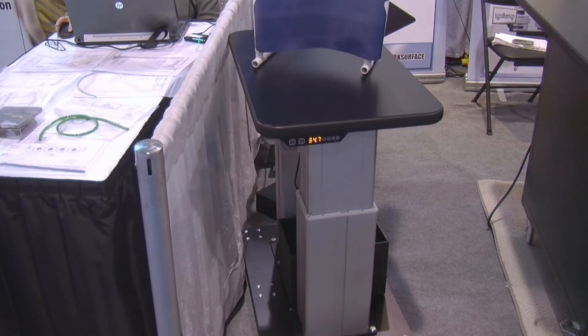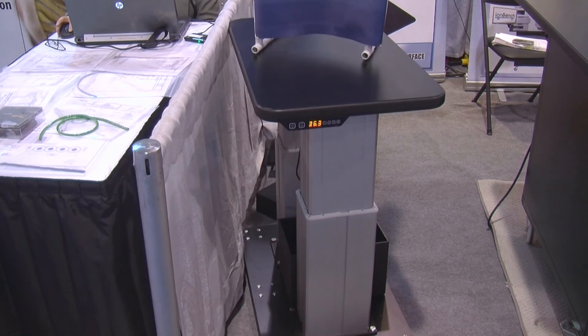The LC cart includes many features such as solvent waste and a power cord at the rear, so that all LC modules are connected directly into the cart. This elevating table comes in many sizes for all types and models of liquid chromatographs on the market, and we also have versions for double-stack HPLCs. For more information, visit our website at www.ionbench.com.